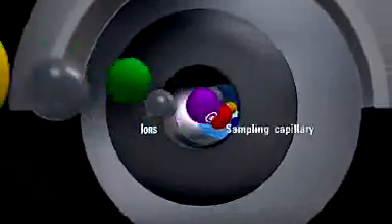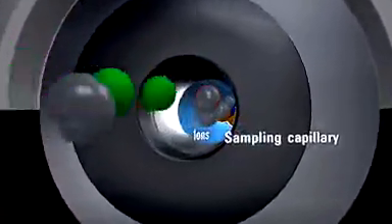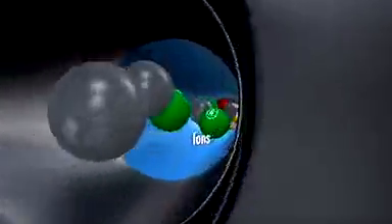High volume counterflow drying gas reduces noise related to incomplete drying of solvent droplets and keeps the sampling capillary and ion optics cleaner for reduced maintenance.